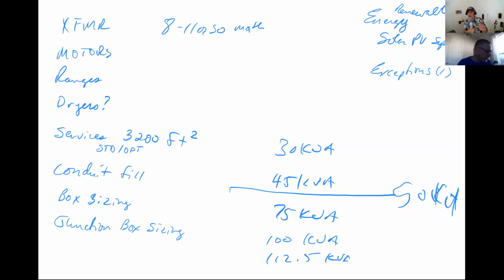I'm not saying that there's not 50 kVA transformers out there, which I think is probably what it is. I think there are some single phase 50 kVAs, but I could be wrong. I've never come across one. Instead of giving you the 50 kVA, which is what's written in the code book, they're saying, well, if I have a transformer rated XYZ, can I put it above a drop ceiling? And so that's what this hollow space installation is really about.